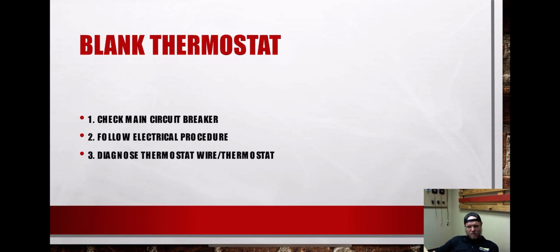Go back downstairs. Reset your breaker. Go back upstairs and then turn your disconnect on. You don't want that piece of equipment turning on while you're not there. It's important to be standing right in front of it, and you're there. You might as well be able to know what happens.